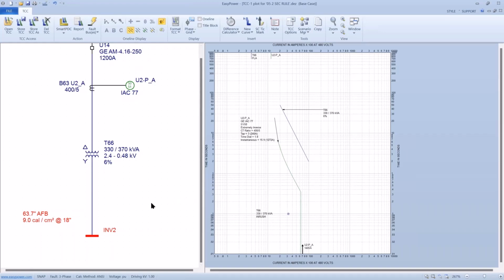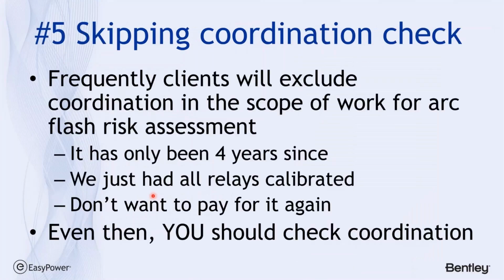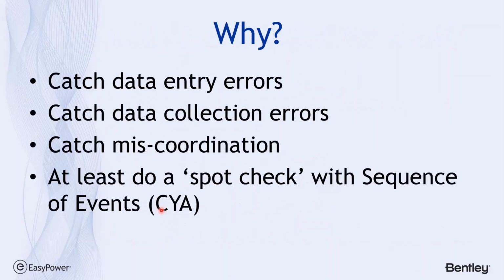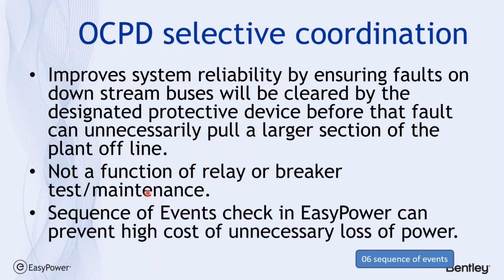Yeah, so my point is, make sure that if you're doing the 2 second max, that you don't skip the coordination. And so at the very least, even if you have had these relays tested, if the client doesn't want to pay for coordination because it's been done only a few years ago, just for your satisfaction or coverage, I think you should be doing a coordination check, because there could be data entries that could be caught. There could be data collection problems. Again, the miscoordination if I'm doing my 2 second max prematurely. And so what I recommend, at least do a CYA check with your sequence of events to get a selective coordination check. So let's see what I got for sequence of events.